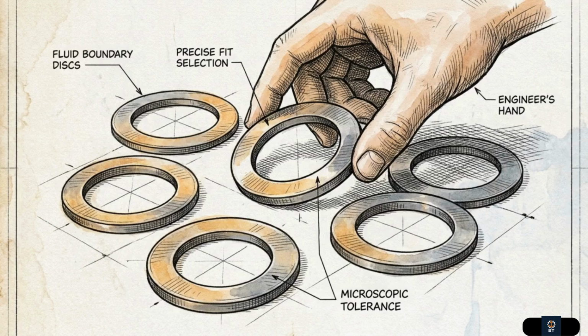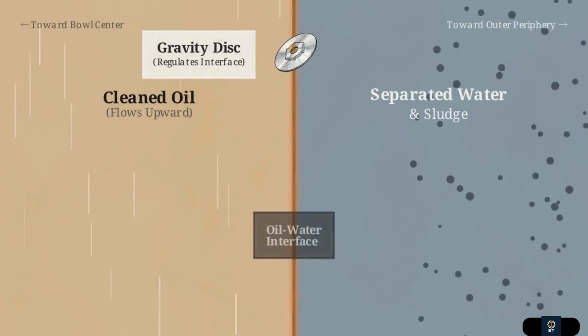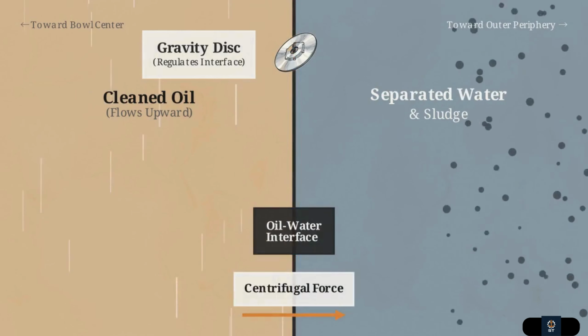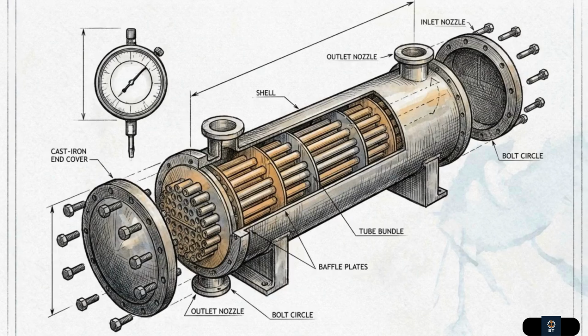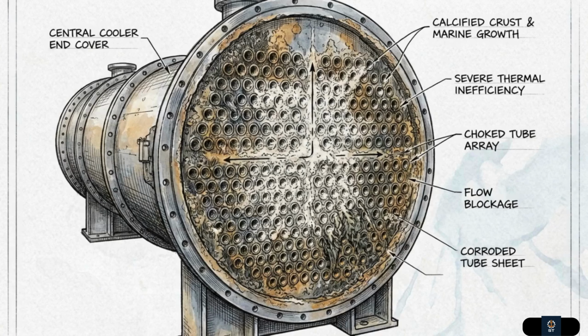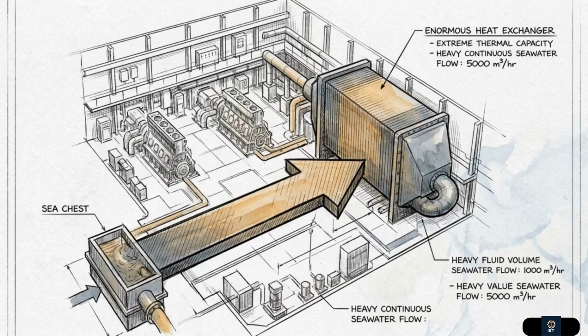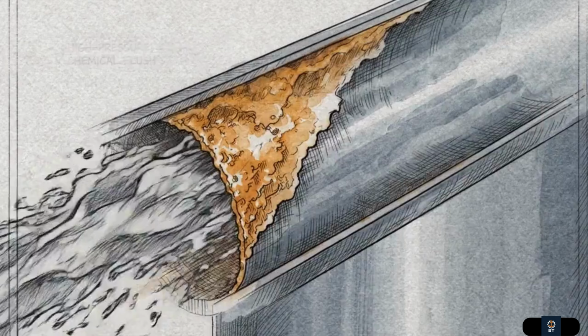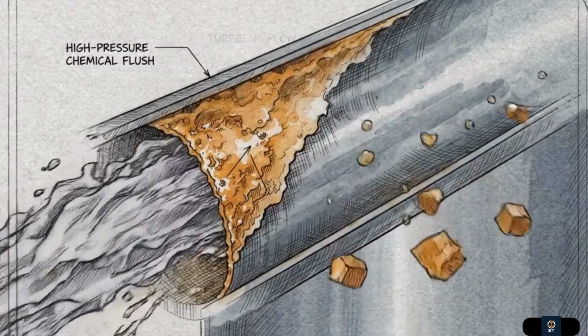The combustion blocks require an intricate network of circulatory and thermal management systems to keep the machinery alive. The centrifugal purifiers sit at the start of the fuel cycle. These high-speed rotating machines spin heavy fuel oil, utilizing extreme G-forces to forcibly separate out water and highly abrasive solid impurities before they can reach the engine. Inside the spinning bowl, the correct sizing of the gravity disc dictates the critical boundary interface. It holds the line between the cleaned oil and the separated water.